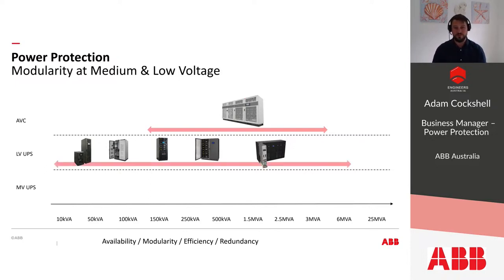Therefore, our DPA UPS family is scalable from 10 kilowatt all the way through to 6 megawatt. Our HyperGuard MV UPS has system blocks of 2.5 MVA with a parallel capacity up to 25 MVA.